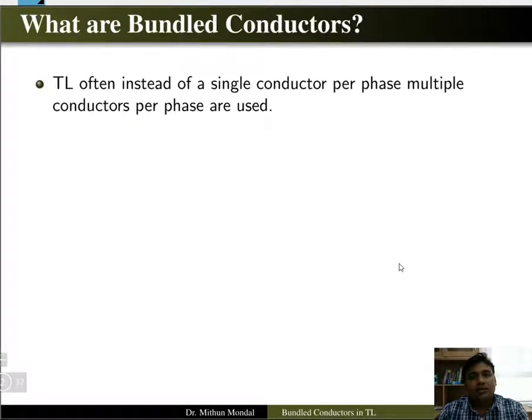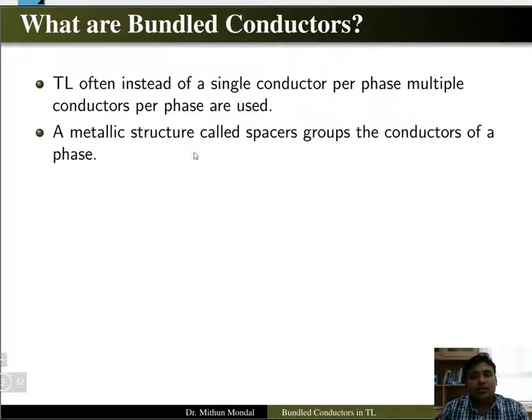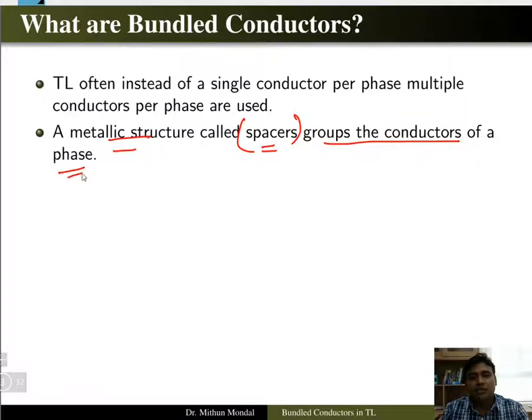So what are bundle conductors? Generally in a transmission line, instead of using a single conductor, we will use multiple conductors per phase. There is a metallic structure known as spacers. Spacers are the metallic structures that group the conductors per phase, so any phase can have two or three conductors grouped using spacers.